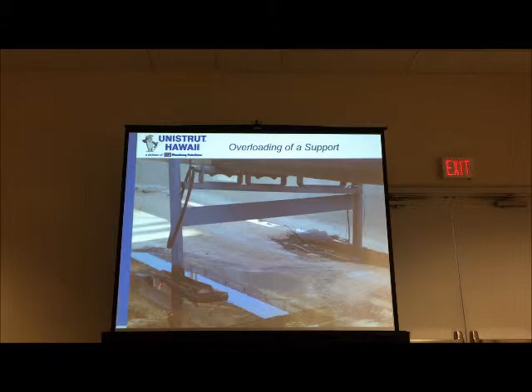More than likely, what has happened here is that they have not considered the entire weight of this service. There are 3 of these pipes, as you can see, 3 yokes here with the roller supports. Because of that, we're still running into this problem where the base, the surface area of this base, is not wide enough or big enough to handle the load being applied to it. So you're getting a failure, and with that failure you're getting pooling of water that starts to drip inside your building.